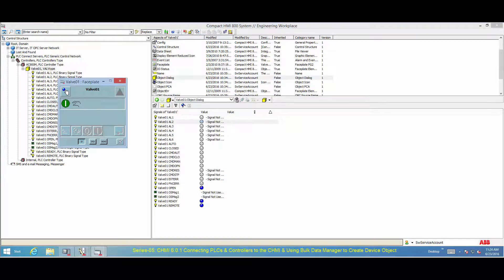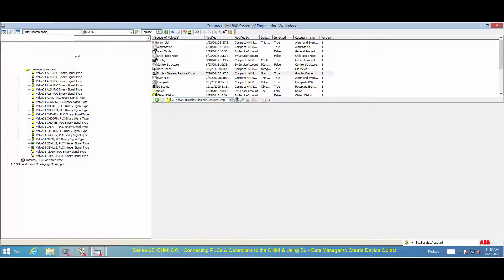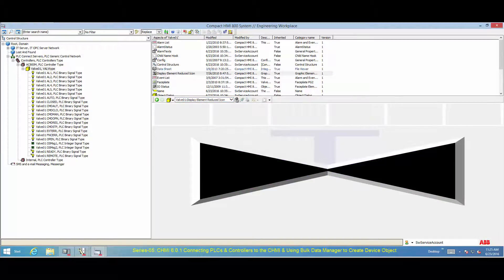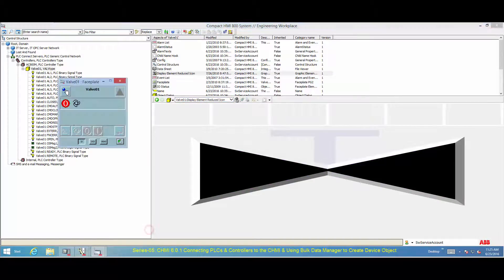In this scenario, the command from the device faceplate enables us to see the signal status live from the PLC. Receiving live values from signals indicates that the PLC Connect functions as required. The display element of the device object also gives you the status of the device.